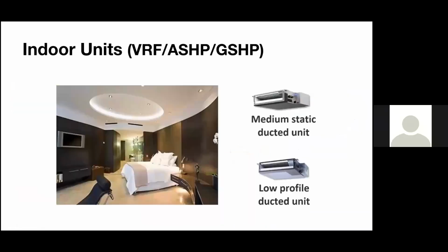And then we go to maybe the more popular units in the United States, and that's because we really can't see them. We don't like to look at what's feeding us cooling and heating a lot of the time. So we like a better aesthetic. But yeah, the first option is the medium static ducted unit. This has a pretty good throw overall. It has up to 0.8 inches of static pressure, so it can do a long route of ductwork. And it stands about 11 to 12 inches tall. So that would be perfect for an office space scenario.